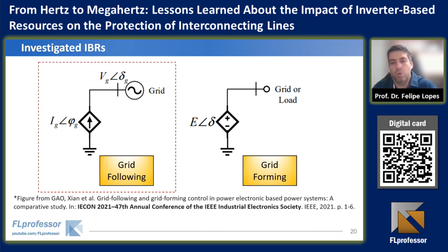So lesson one was: blind zones on the interconnecting line may exist if communication is lost. It is not new information, and it generated a paper which we presented at DPSP in Liverpool. There we were evaluating real devices, considering some protection functions from the perspective of the number of operations and operating times. In this paper, basically, we took into consideration a traditional interconnection system. Like here, we have the power network at the right side, and here the IBR connection.